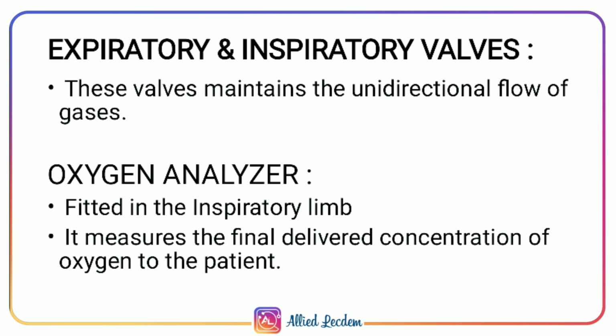Here, the inspiratory valve prevents the backflow through the inspiratory limb during expiration, and the expiratory valve prevents the backflow through the expiratory limb during inspiration. Therefore, these valves maintain a single direction of flow of gases. O2 analyzer. It measures the concentration of O2 delivered to the patient and is fitted in the inspiratory limb.